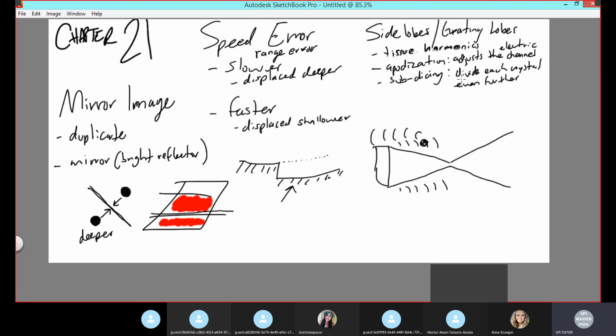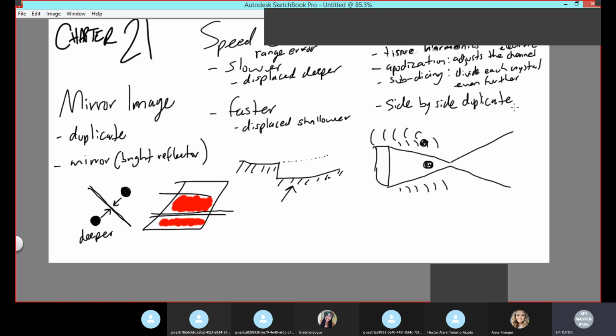Okay. The machine assumes that all reflections come from your main beam axis right here. So the machine says anything that comes back to me is from my main beam axis. So when you have this little bright reflector return an echo, the machine says, oh, I have a reflection. You must be in my main beam axis. Okay, so it's going to create this side by side duplicate. It's not going to put it deeper or shallower. That's not going to happen because there's nothing about propagation speed here, which is what influences where something is. This is simply duplicated and moved to the main beam axis. It's supposed to be on the side, but the machine assumes that things do not come from the side.